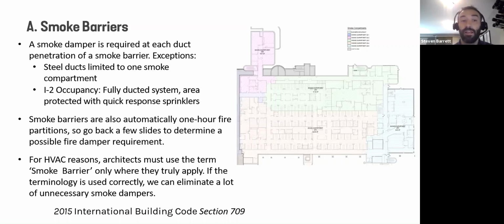Also important to note that smoke barriers are also 1-hour fire partitions. So you may also be required to provide a fire damper unless you meet one of those exceptions. And again, just the importance of terminology, smoke barrier is relatively rare. You'll see them a lot in hospital projects, but it shouldn't be used unnecessarily, or it may cause there to be more smoke dampers than necessary.